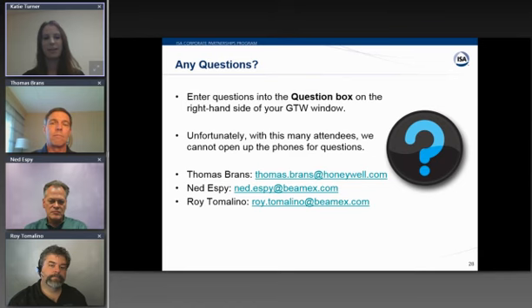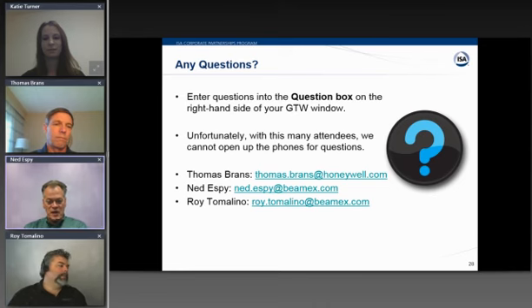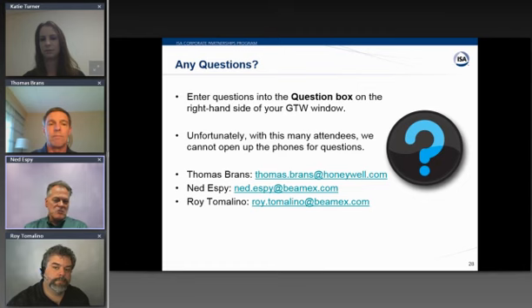Okay, and it looks like the last question we have is, how do you measure drift of an RTD? You have to make measurements over some period of time. If it's a critical measurement, maybe you need to check it once every few weeks or once a month. Maybe if it's not so critical, say every 6 months or once a year. Typically, after you've made 3 cycles, you're going to see a pattern. Is it drifting to the north? Is it drifting south? Or is it pretty well flat?